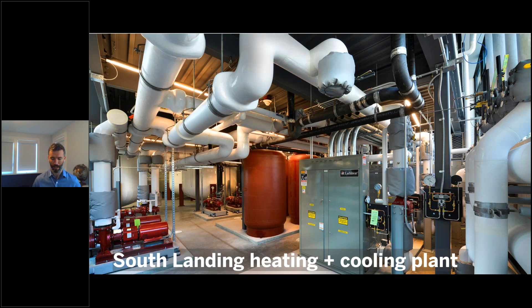As the envelope of the building becomes more efficient — and it's a shame Brad didn't have time to talk through some of the really cool aspects of Catalyst — the annual need for heating and cooling is reduced. So for our campus, even in the winter months, a large proportion of the heating needs are met by internal gains and heat recovery. We have a cooling dominated system, even in a cold climate zone like Eastern Washington. To that end, the selected chilling system has high efficiency and does the lion's share of cooling. What you're seeing on this graph is the space conditioning load served by the central plant: above the axis is the cooling load, and below the axis, the heating load. Next slide, please.